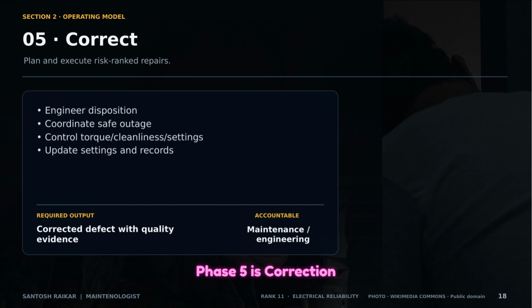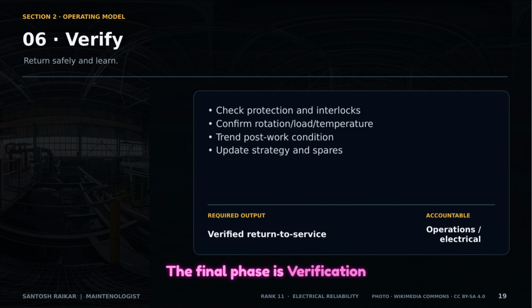Phase 5 is correction. When defects are found, they must be risk ranked. Maintenance and engineering work together to coordinate safe outages and ensure that repairs, like torquing or cleaning, meet the required standards. The final phase is verification.